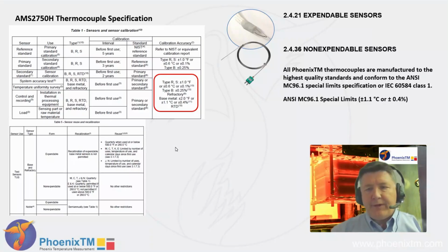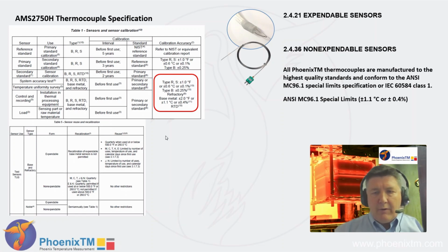As part of the AMS 2750 CQI-9 temperature uniformity survey, a critical requirement of the work is to ensure that the sensors being used with the field test instrument or the data logger are within specification and accurate enough to give you confidence in the data that you're providing. Within the standards themselves, there's a clear documentary requirement as to the type of sensors that can be used and the specific accuracy that needs to be achieved for the use of those sensors.